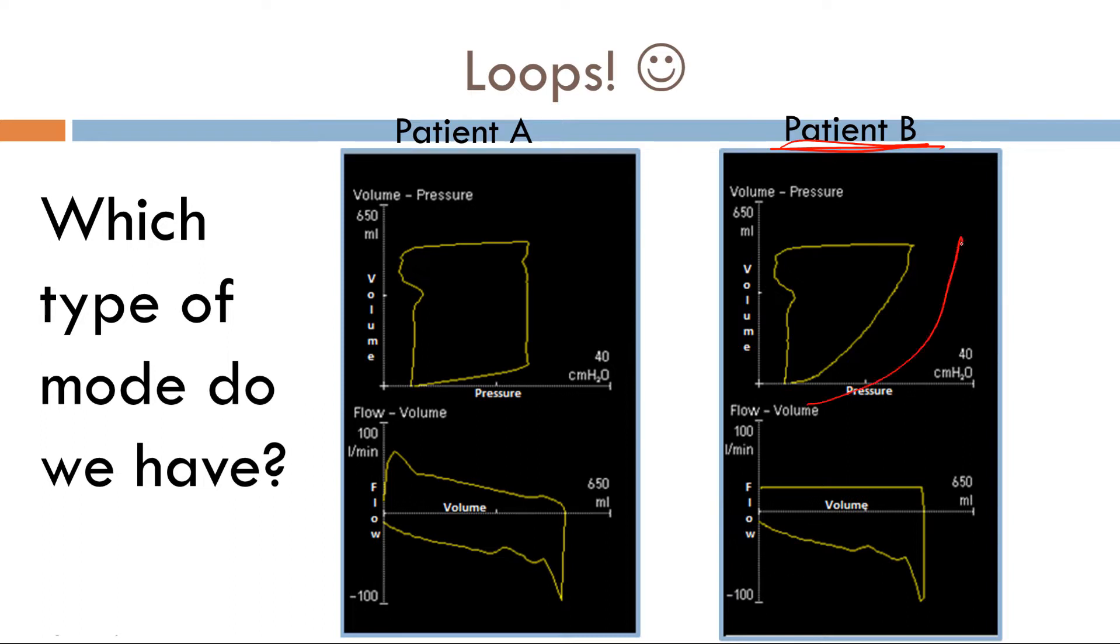So again, we have inspiration here, expiration here, inspiration here, expiration here. Now, during the inspiratory phase, the target variable should be constant. So look right here. Flow is completely constant during the inspiratory phase here.